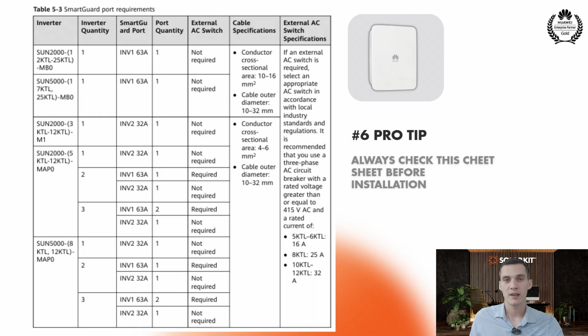We recommend connecting everything to the backup load, because there's basically no disadvantage to that. On top of the smart guard there's a switch you can turn down if you want to exclude the whole inverter system, for example due to some hardware malfunction. Then you can connect the household directly to the grid, as if the inverter weren't even there. That switch powers not just the grid output but the backup output as well.